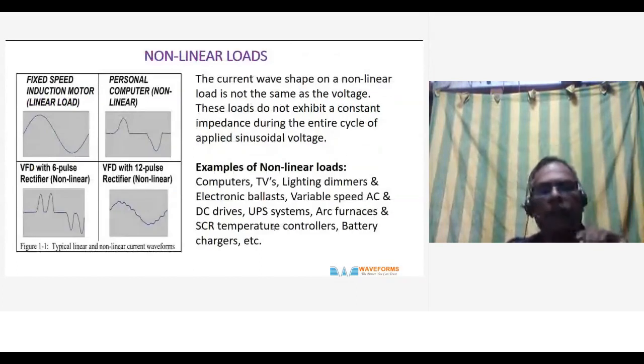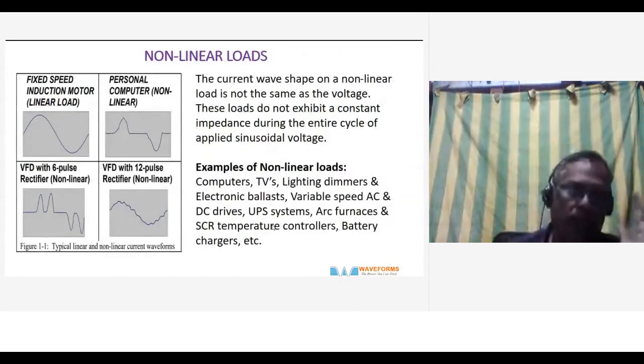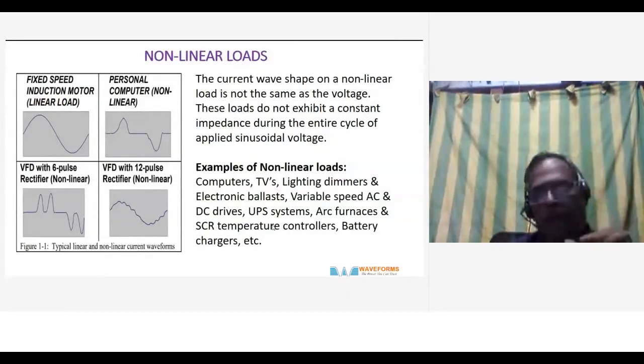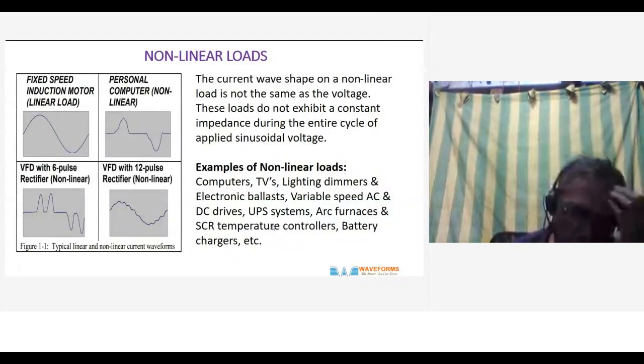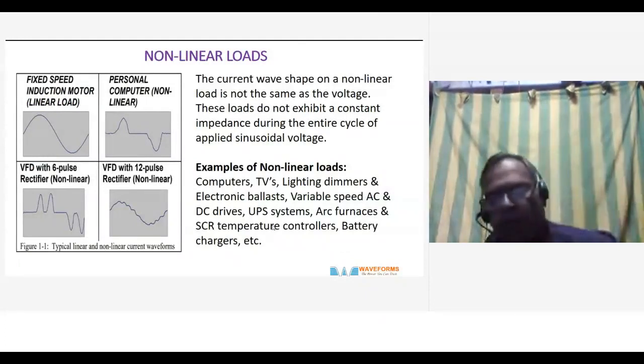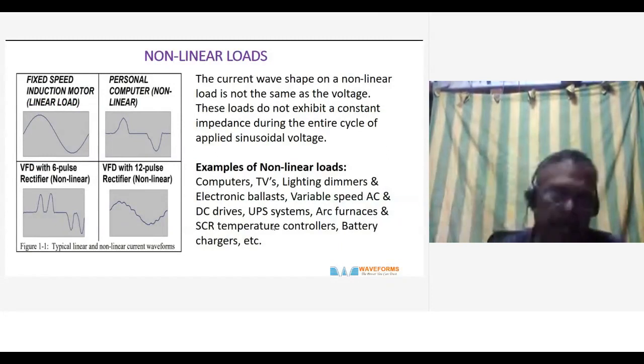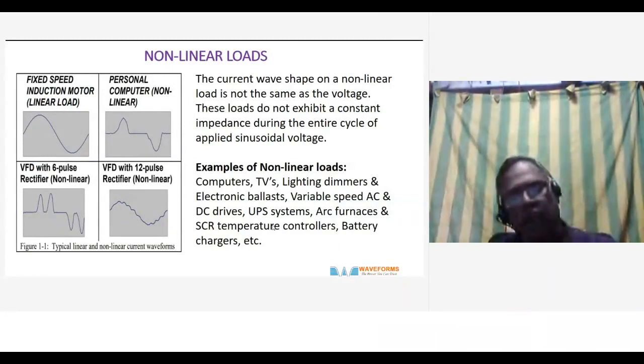So that is the linear load. Now the subject of harmonics arises only because of non-linear load, because due to automation, robotics, and other power electronic equipment to improve efficiency.